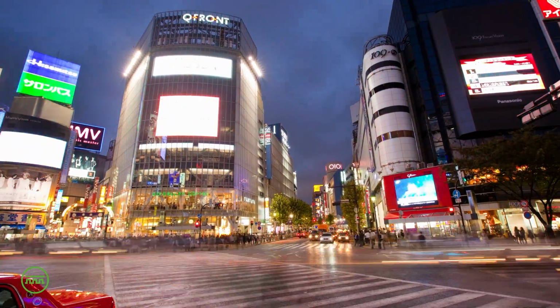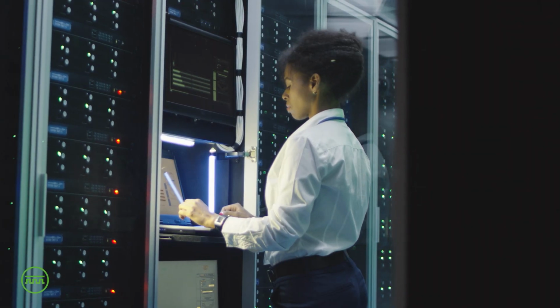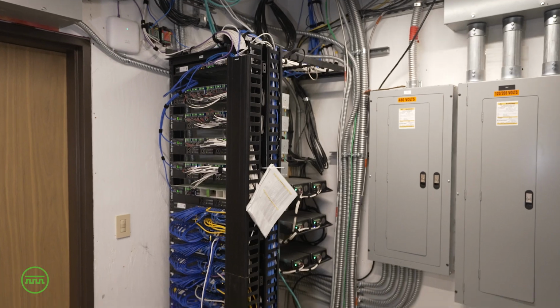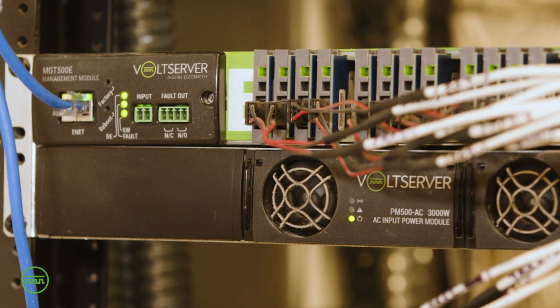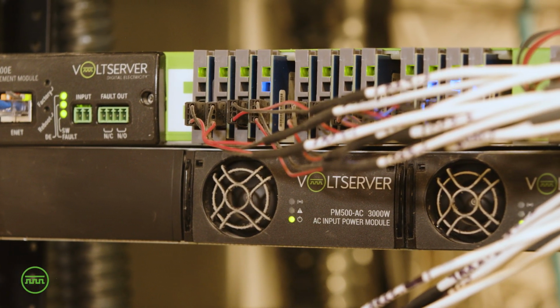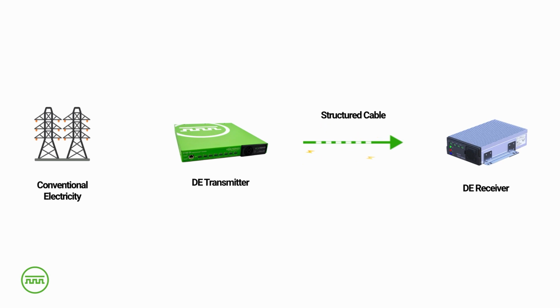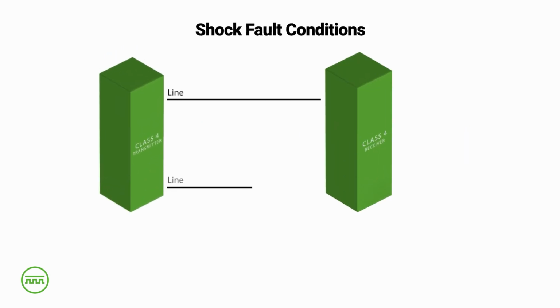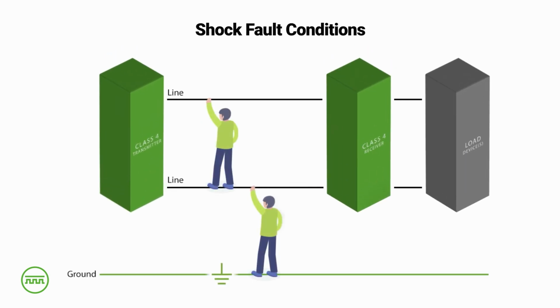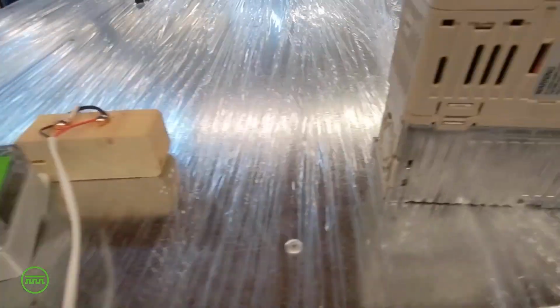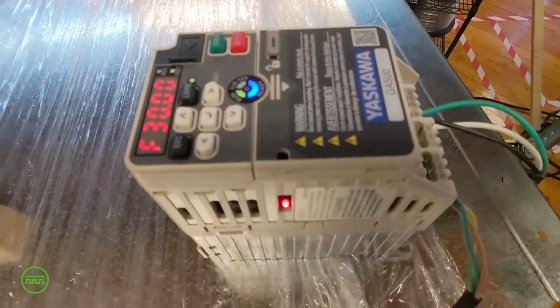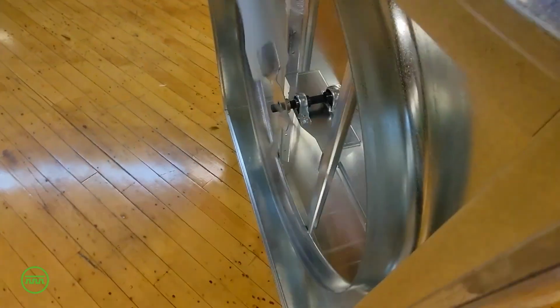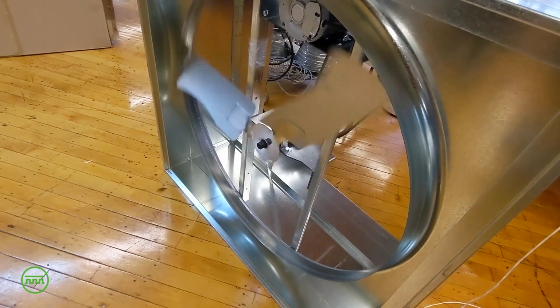Just like today's buildings are becoming more intelligent, fault-managed power systems are also more intelligent than previous forms of power. They constantly monitor for faults and control power current delivery during abnormal conditions to mitigate the risk of shock or fire. Fault-managed power is the only technology that can detect touch faults, also known as resistive faults, and line-to-line faults. This means they can tell the difference between the electrical load and a human touching the wires.